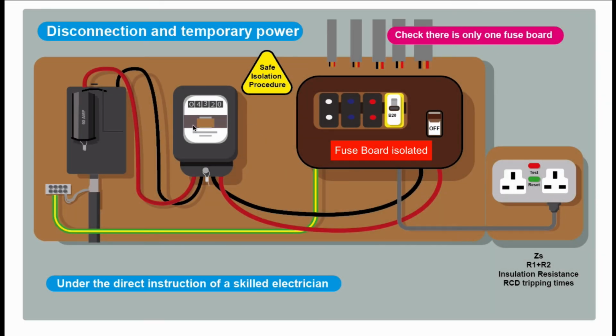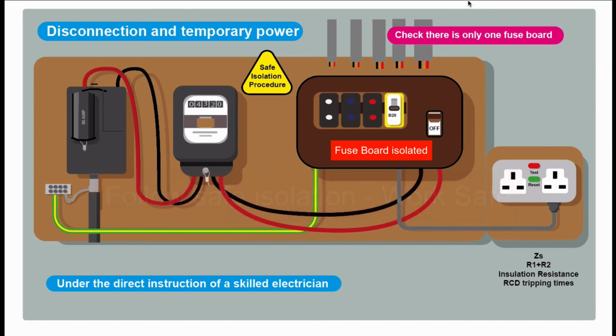Okay, so the meter people can't come and fit an isolator for a couple of weeks, but that's okay. It's not going to stop us cracking on and getting some work done. What I generally do in that situation is I'll keep the old board, because obviously we can't put the new one in because the tails are going to be live, and I'll utilise one of the circuits in the old fuse board. I generally strip everything out, pull all the conductors out, all the cables out of the old fuse board, so we know that everything in the house is dead, so we don't have to worry about that anymore.